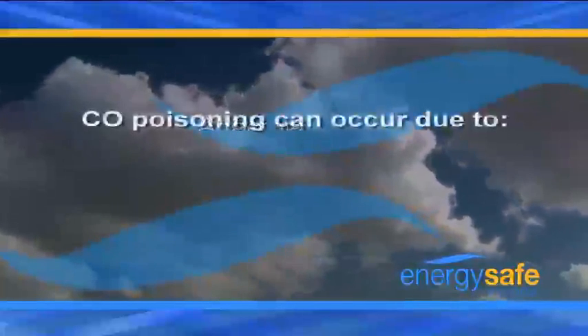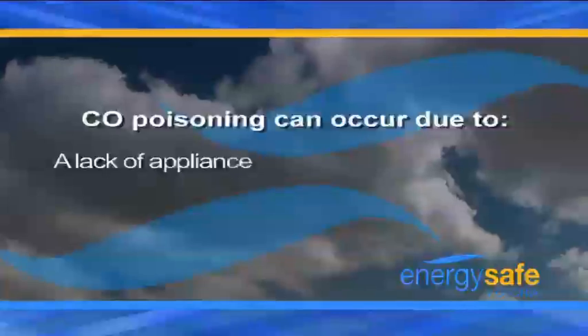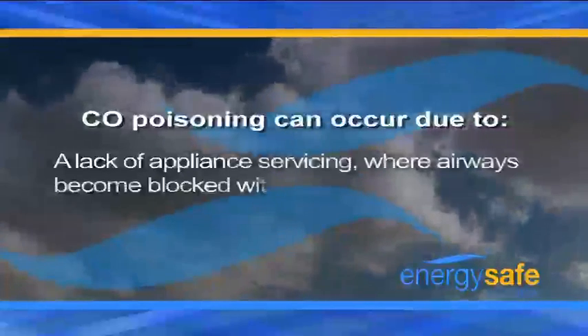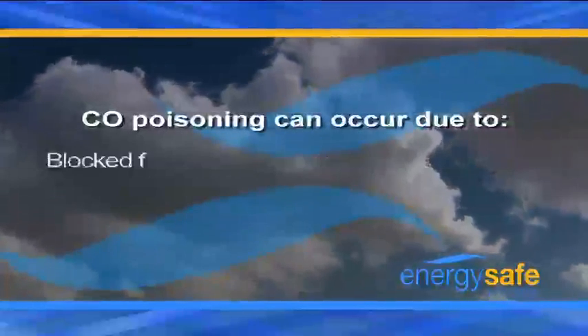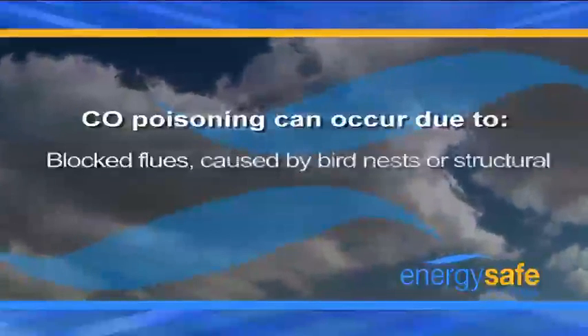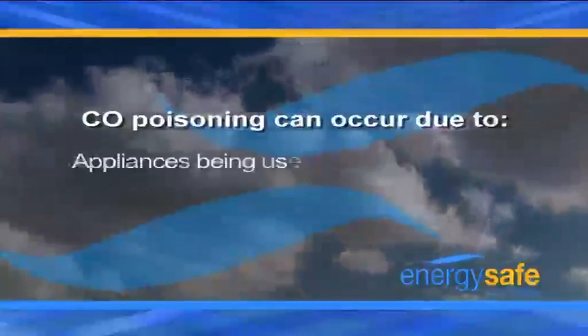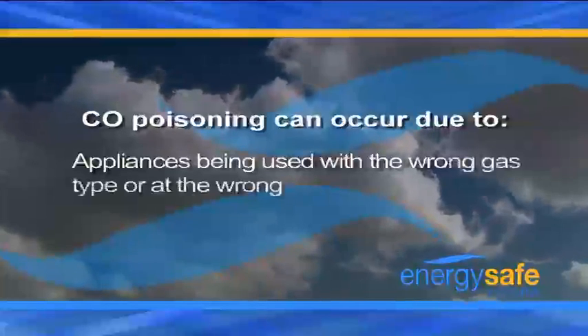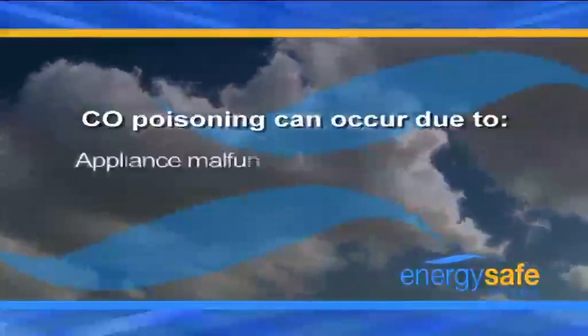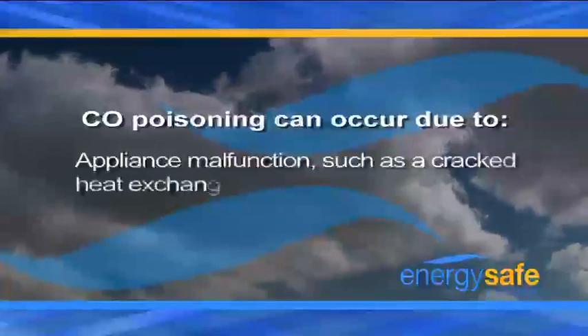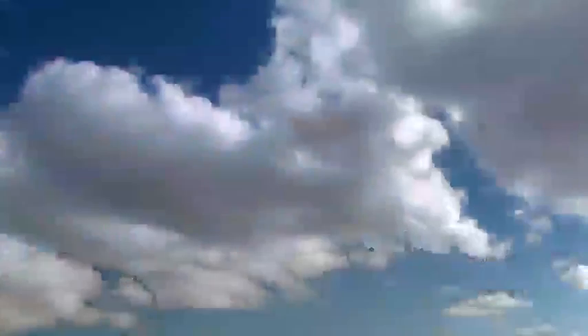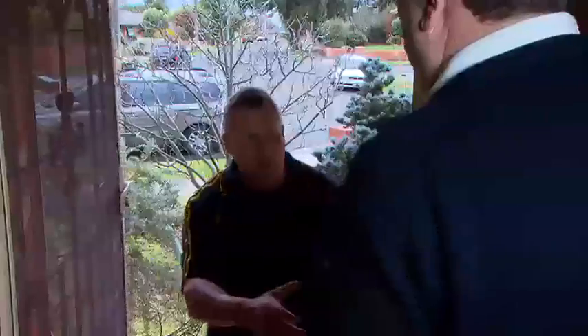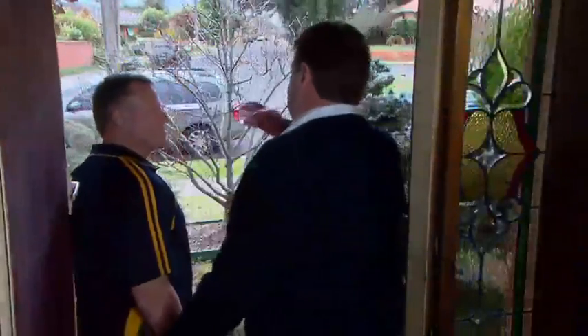CO poisoning can occur due to a lack of appliance servicing, where airways become blocked with dust or lint, blocked flues caused by bird nests or structural failure, appliances being used with the wrong gas type or at the wrong pressure, or appliance malfunction, such as a cracked heat exchanger. All these situations can cause combustion products to spill into the atmosphere. This program is designed to assist gas fitters to ensure appliances are properly checked so that heaters remain safe.